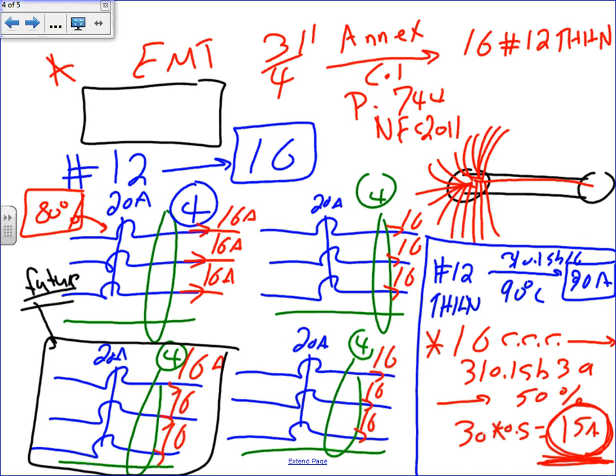This system will give me 20-amp branch circuits, right? Based on this, I can have 12 20-amp branch circuits. Are you with me? If you decided for future expansion to drop one of these three-phase circuits, that'll give you 9 branch circuits, right? I'm going to start with the 12 branch circuits in 3/4 of an inch.